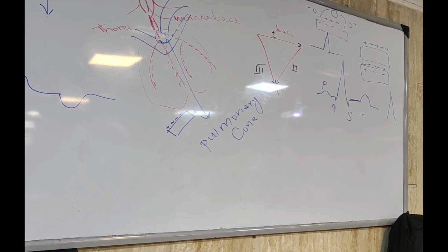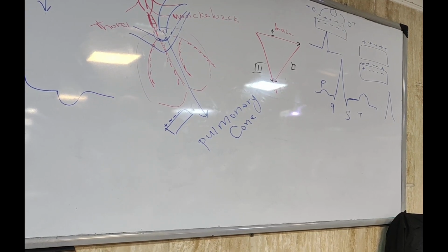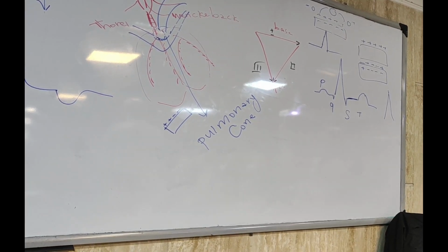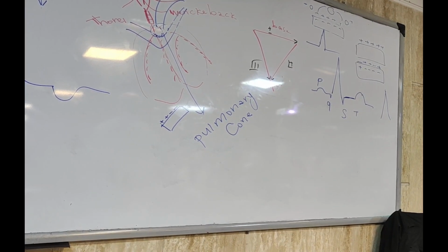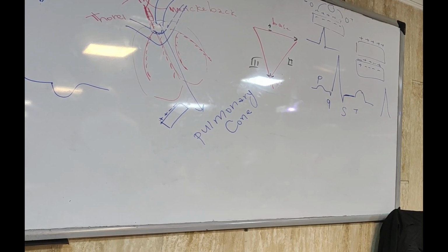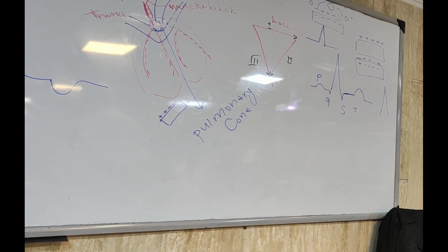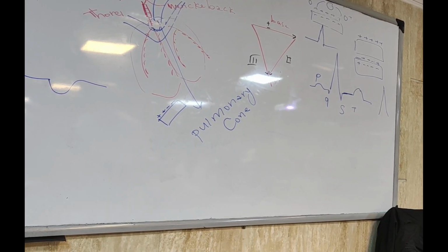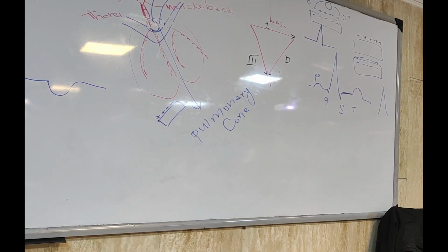This electricity makes some noises, so you should eliminate them. Connect the right leg to the earth in order to eliminate unwanted noises. Electrocardiography is very sensitive to noises. Even fluorescent lights make some noises. So connect the cable to the ground.